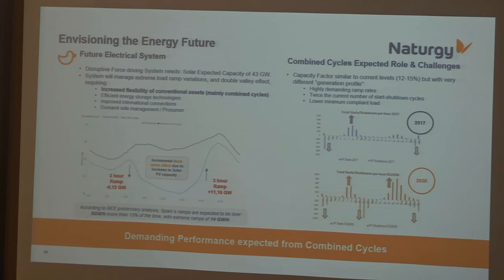But the operation profile of the power plants will be much different. They will need greater ramp rates to accommodate this residual demand, and will need to start up and shut down much more frequently than today. The initial analysis shows like a doubling of cycling from current levels. The average plant in Spain now makes around 60 starts per year; that will mean the average plant in the future will make 120. And we have extreme cases that are currently doing like 200 starts per year.